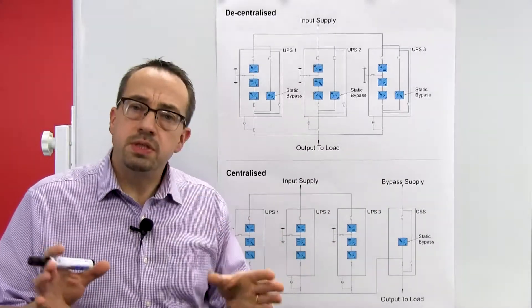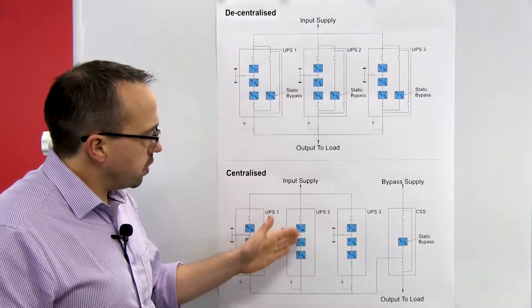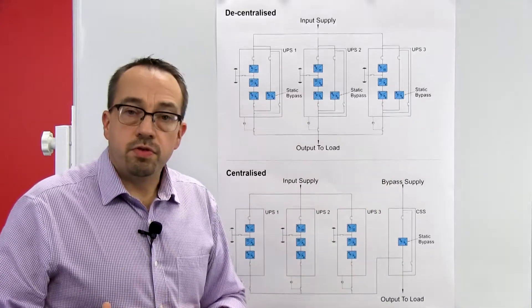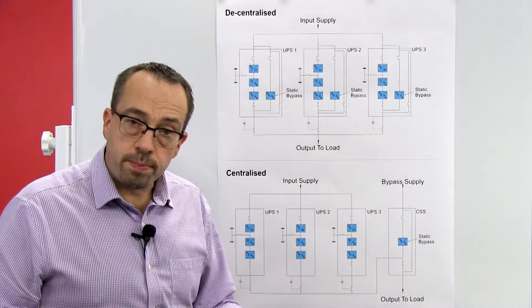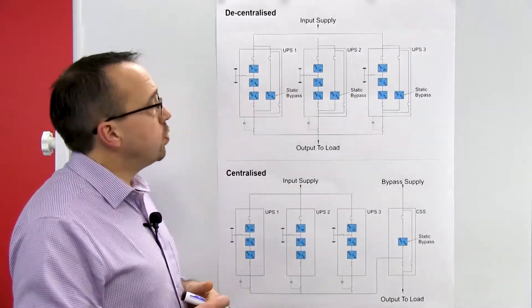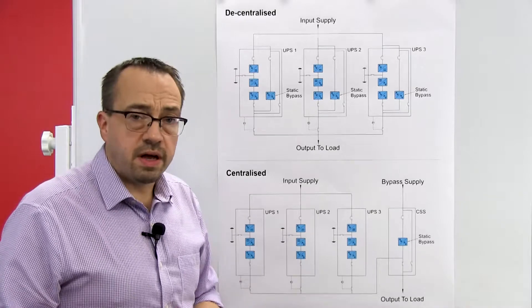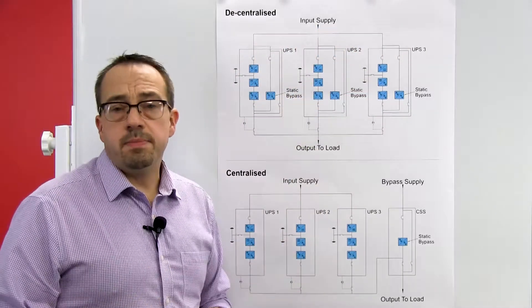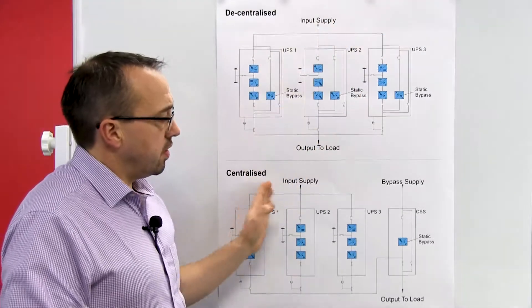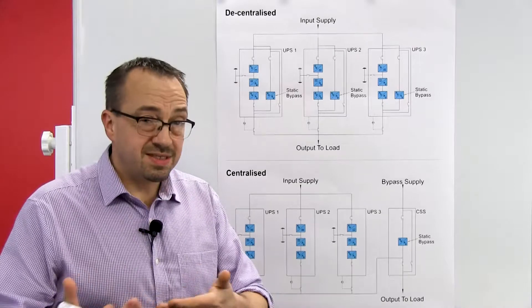There is something important to consider: the centralized system is effectively dual input, because the rectifier modules are fed from one source and the bypass module is fed from another. If you wanted to apply that same dual-input approach to the decentralized solution, you would have to increase the breakers feeding each UPS to two — one for the rectifier and one for the bypass line — meaning the switchgear would need six input circuit breakers in total. This additional switchgear cost is typically overlooked.